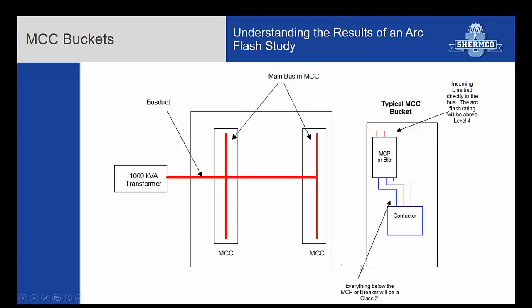Here from the transformer all the way to the MCC, it would be class 4 is what we got when we did this study. So every bucket plugged into either one of these MCCs ended up with a class 4 rating on them.